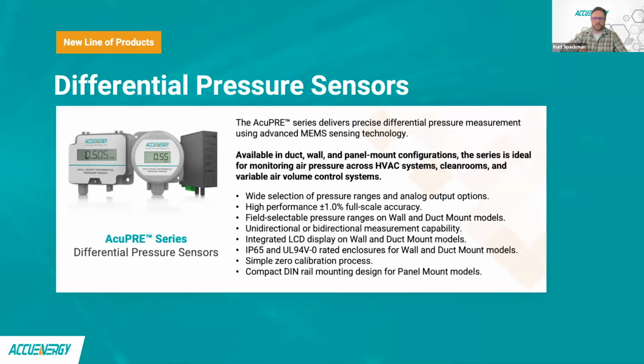We do have a wide selection of pressure ranges available in all the different products with multiple industry standard analog outputs: 4 to 20 milliamp, 0 to 10 volt DC, and 0 to 5 volts DC. We standardized with plus or minus 1% full scale accuracy across the entire catalog. We have multiple installation options, user configurable options with field selectable pressure ranges, unidirectional and bidirectional configurations, field selectable response time, and so forth. We have the integrated LCD on the wall mount unit and the duct mount unit. We standardized with an IP65 enclosure with the two units I've aforementioned, and similar features to what the industry demands. For example, simple zero calibration with just a button on the PCB to auto calibrate the unit.